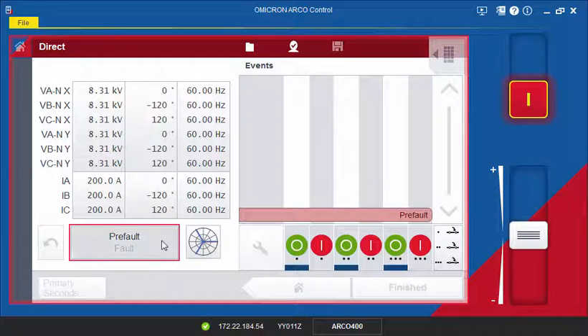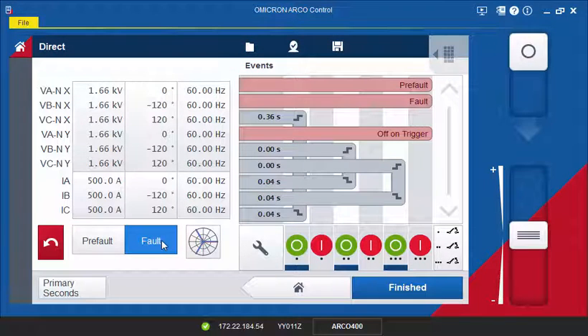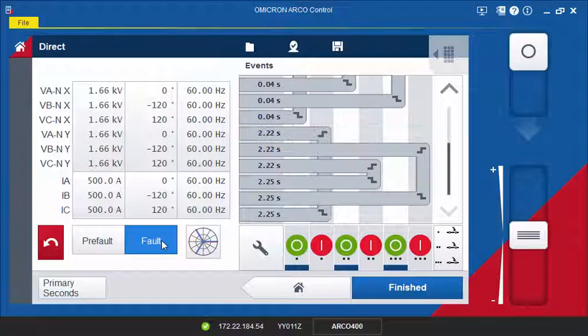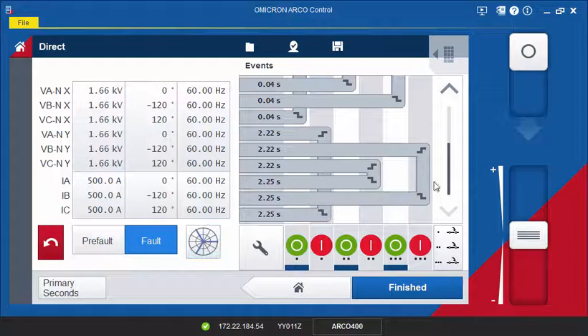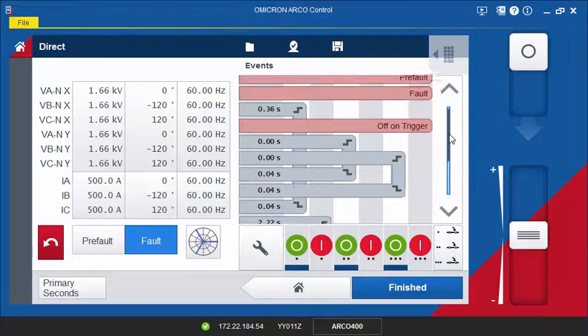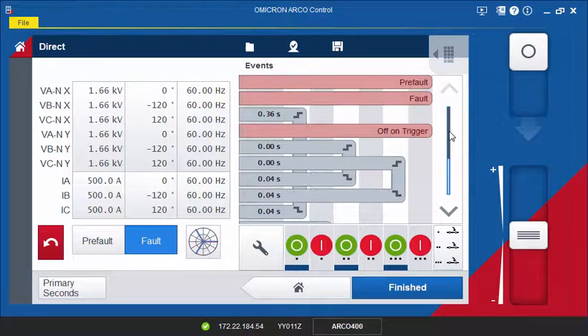Switch to the fault state. The controller trips at the defined fault current and sends an open command. This is shown in the events window. Since the off-on trigger function was defined for an open command, the outputs are turned off as soon as the open signal is received.